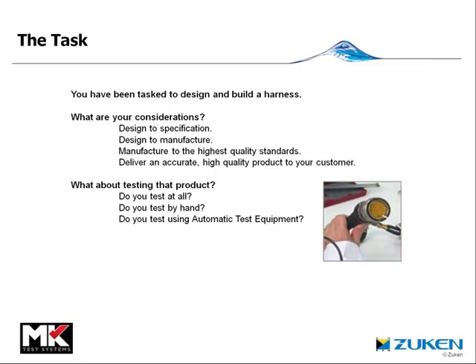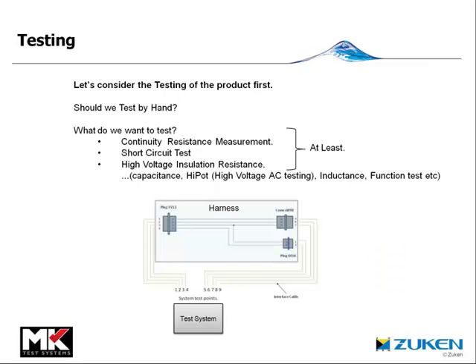So what do we consider? Do we test it at all? Do we manually test or do we use an automated system? At the very least we should measure continuity resistance, short circuit measurements, and insulation resistance measurements. We could of course measure capacitance and impedance, but when manually testing we would probably leave those out.